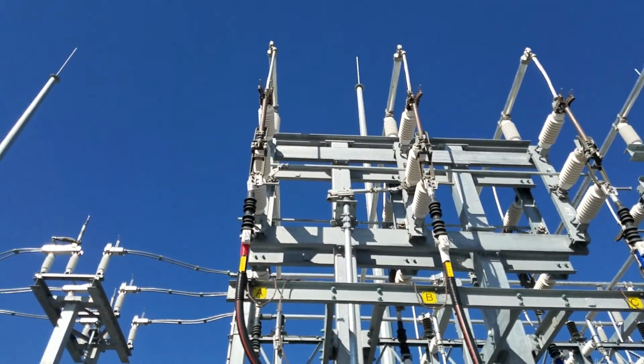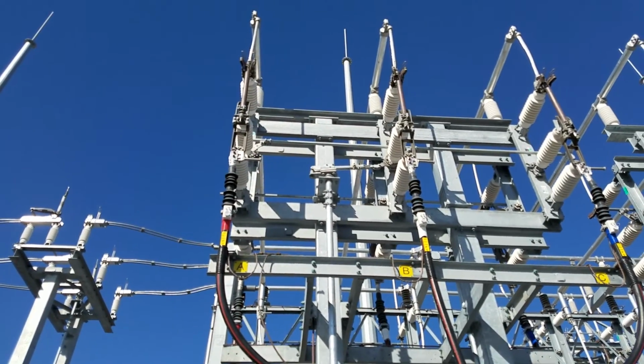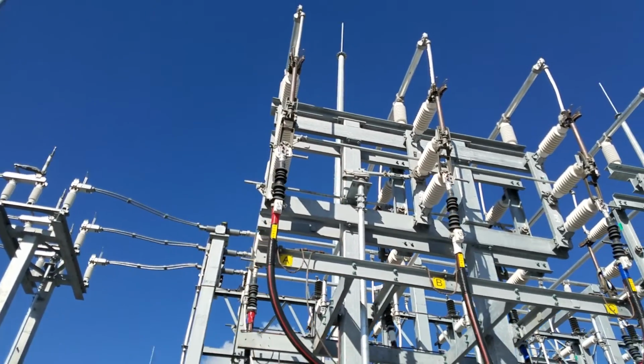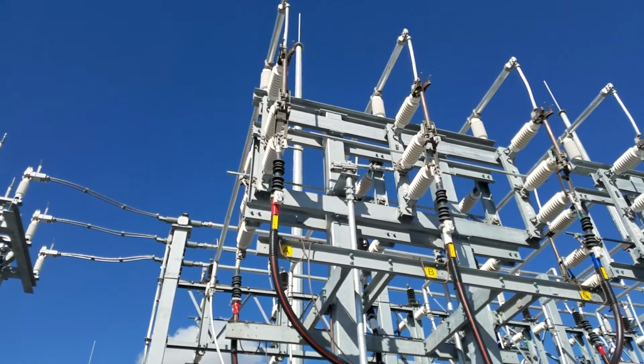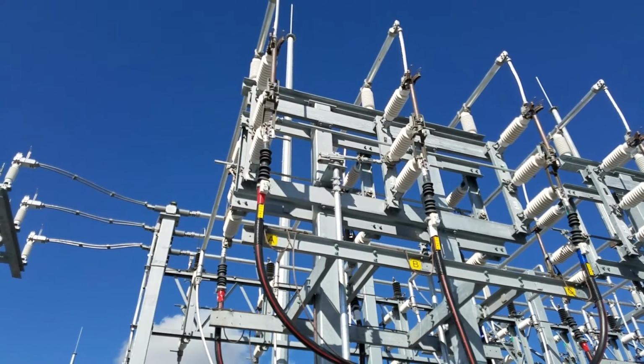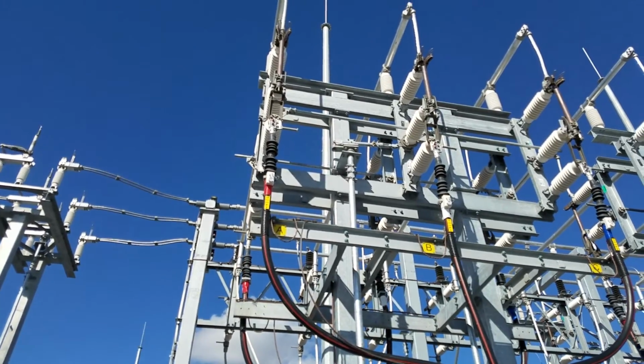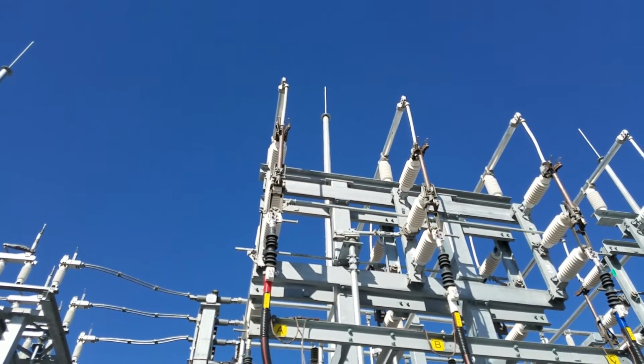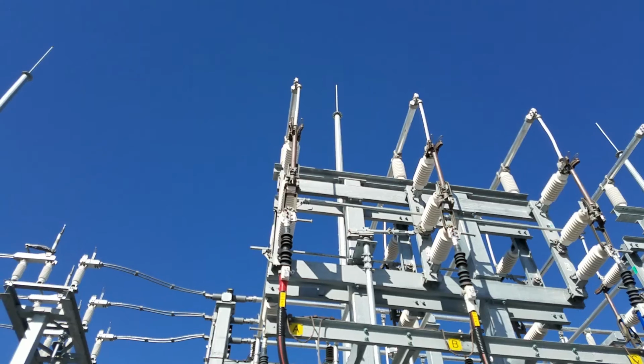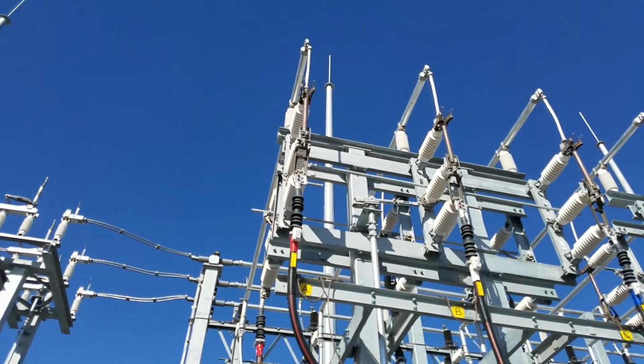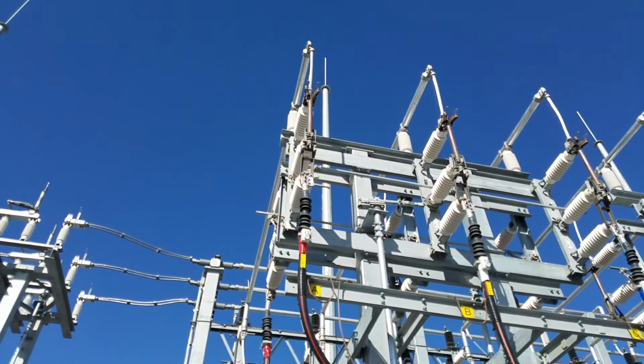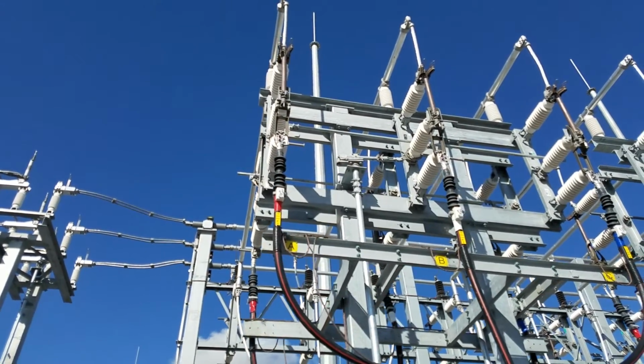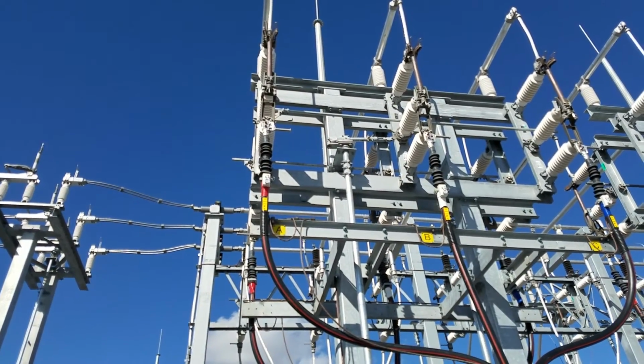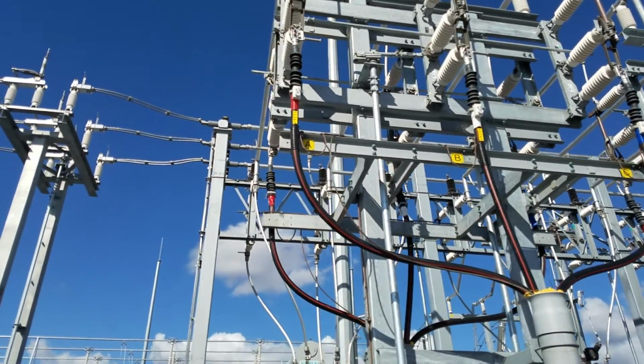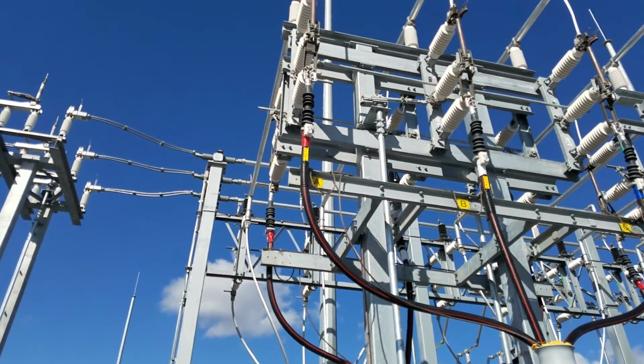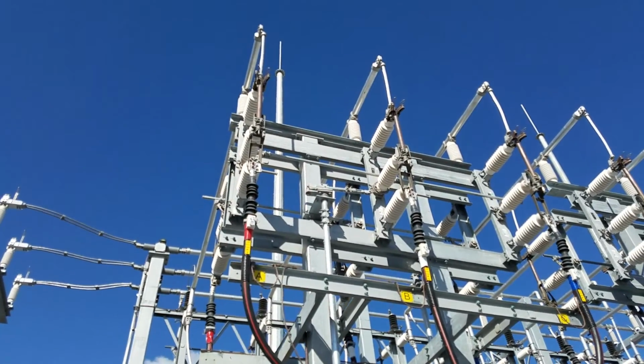What else is here? Those little tabs that are sticking out to the right on each of those paddles, that's for grounding, so you can put your ground cluster on there. So when you're working on it, it can be grounded and you'll be safe from any potential. So if somebody closes the switch, it's looking closed right now, but if it was open and you're working on it and somebody goes to close it accidentally when you're on it, it'll hit the ground and it'll bleed that voltage to ground and trip the breaker before that voltage gets to you. As long as you're not in between the grounds, but you're not here in this case.